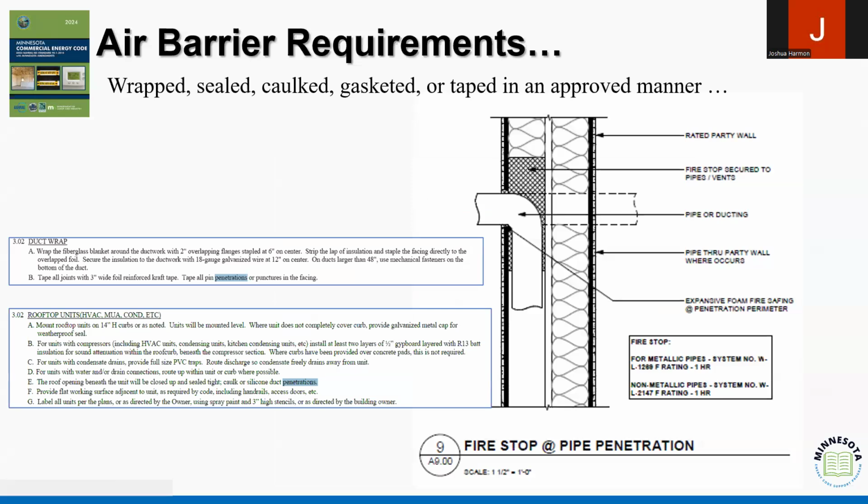I see a lot of this show up when I look at fire details, right? If I see a fire detail project, I usually take the extra step and say, if we're protecting against smoke, we're protecting against air. I had a project where there was a sheet of fire stopping. I'm not going to require you to put a second sheet of air stopping, of air penetration. I'm going to verify that these different materials will qualify for air barrier control, and just let it go, right?